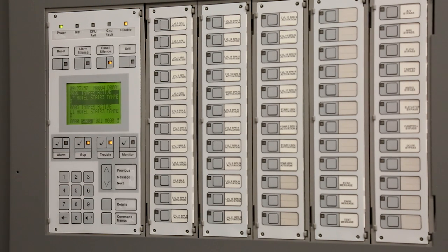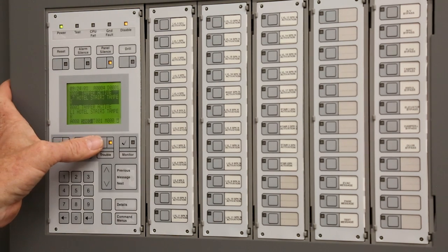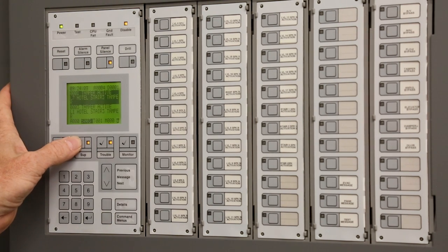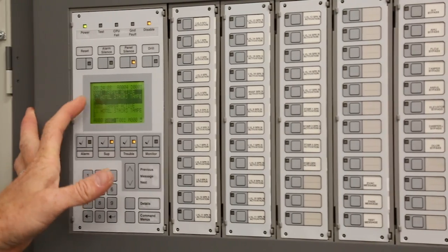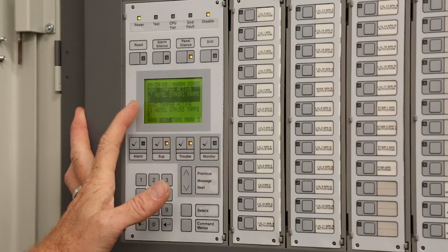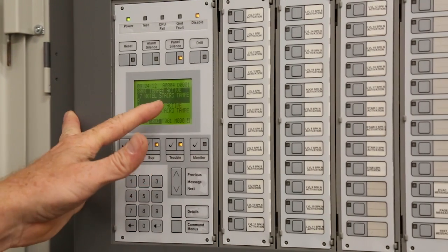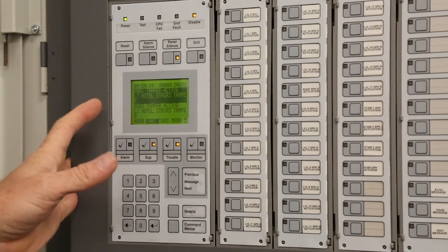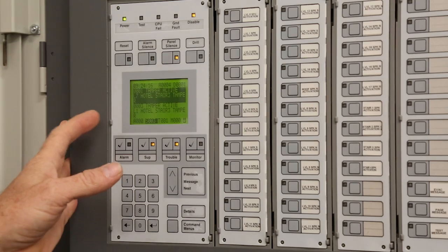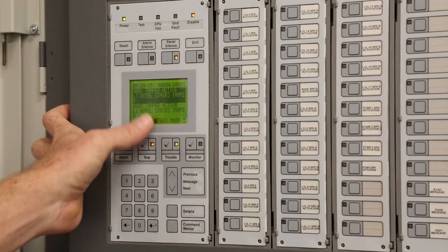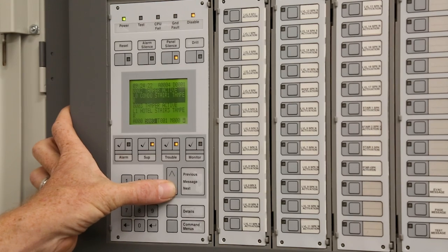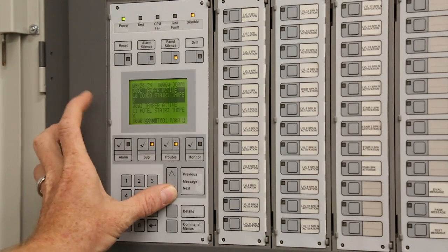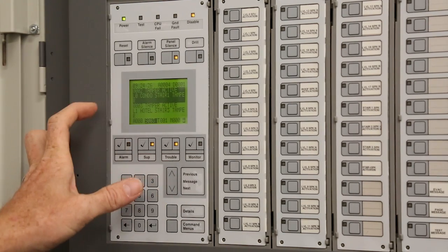Right now, for instance, like I said, we already talked about the trouble with supervisories. Right now, they have a couple valves shut. And it will actually tell you that it's a tamper active. So basically the control valve for the level 7 hotel stair 3 tampers, it's closed right now. They have an issue with it. You can scroll up and down. The first one always comes up right there. You can scroll down, that's your second. Obviously you have 3 right now, that's your second one.